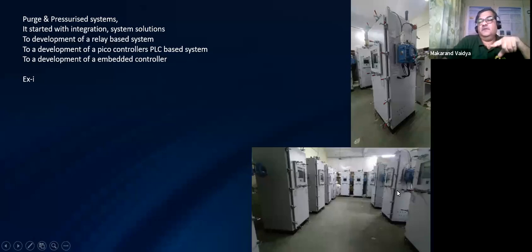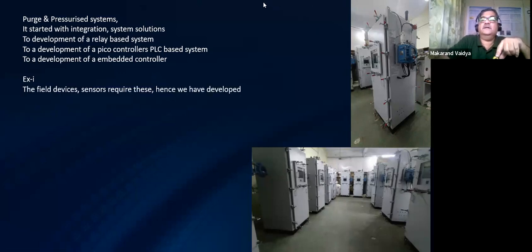ONGC is the end user. This is actually a controller, and it keeps this enclosure in compliance with IEC IS 60079-2. It deals with all those parameters and measures to fulfill the requirement of EXP, that is a purging and pressurizing system. There is one method in which you have to deal with that.